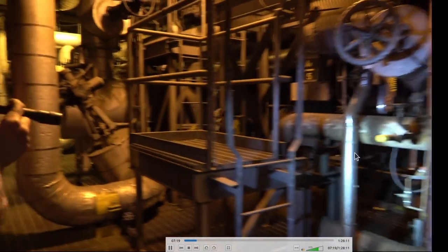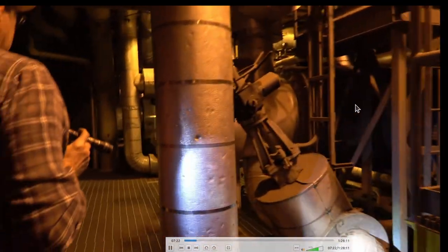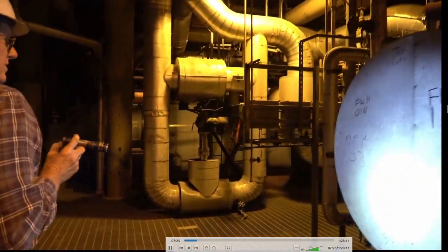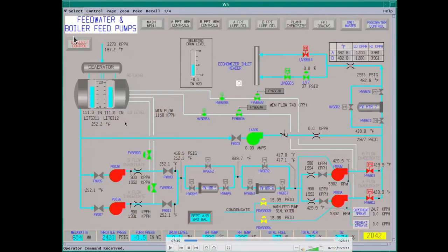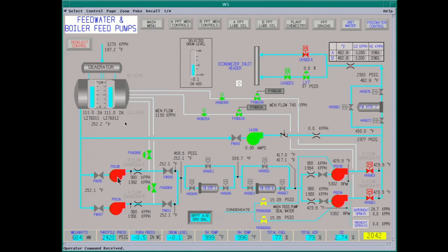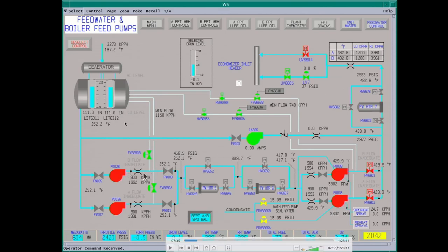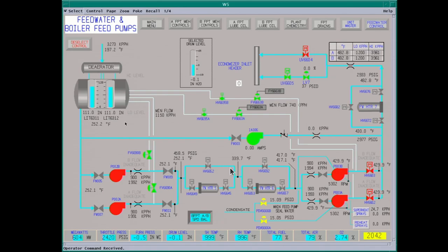This is one of the feed water heaters 1A on the end of it — they've got level transmitters. If there's a high level, they're set to dump to the surface condenser. Here is the feed water system. You have your deaerator on the ninth floor. Water comes down to your booster pumps on the second floor — these pumps run 3,600 RPM and have a gearbox on the end of the shaft. Your main feed pump will run up to 5,825 RPM, driven by a steam turbine that puts out somewhere around 14,000 horsepower. These pumps can put out up to 3,400 PSI.